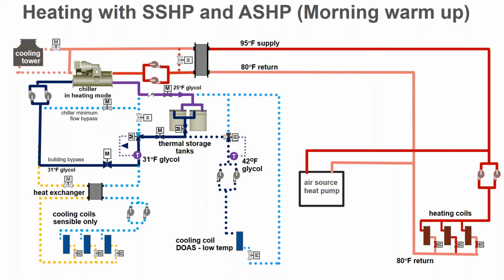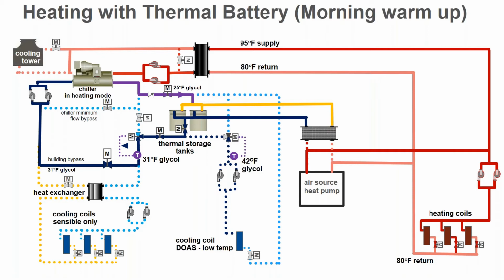The other impact that you can have on these air source heat pumps is, what if it starts snowing? You have this really cold coil that's trying to make the air even colder. You have to get into different things like melt and defrost cycles. So they are subject to the elements. Well, one of the things that storage allows you to do is spread this load over time. And so I threw on just a heat exchanger, and now the air source heat pump, if it has extra energy to give, maybe it could be a source for melting ice and storing that energy for a later usage.